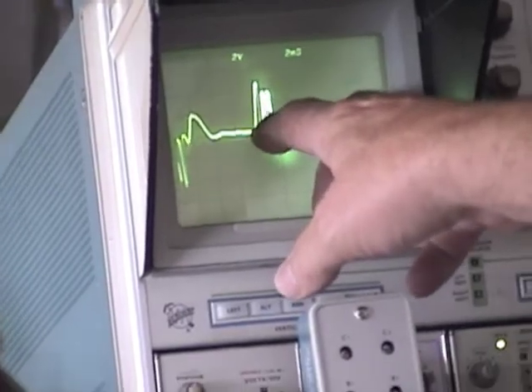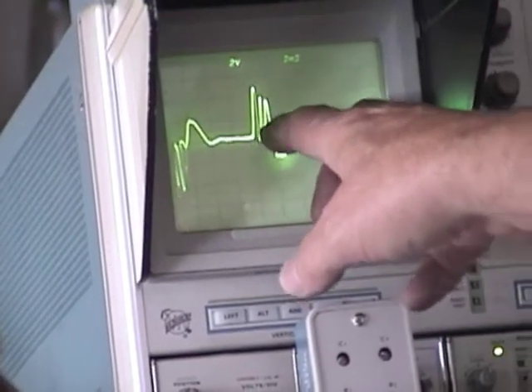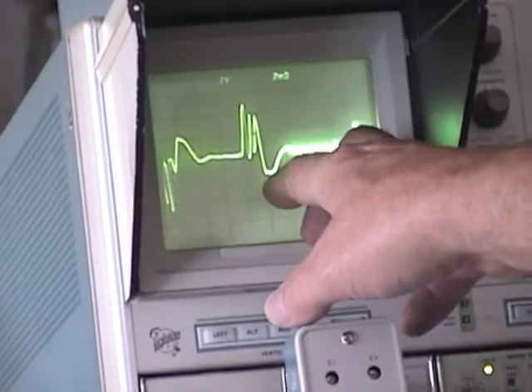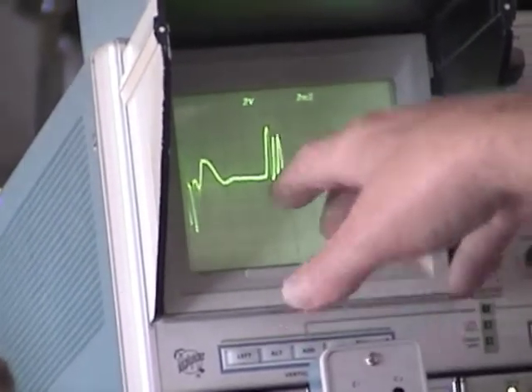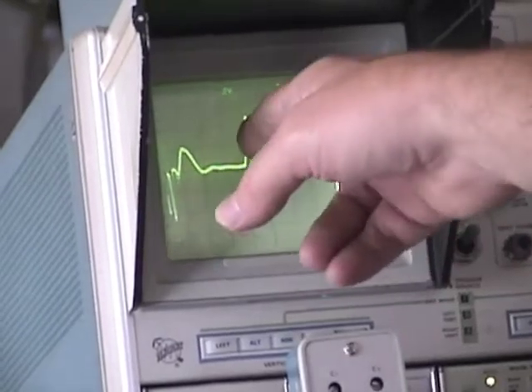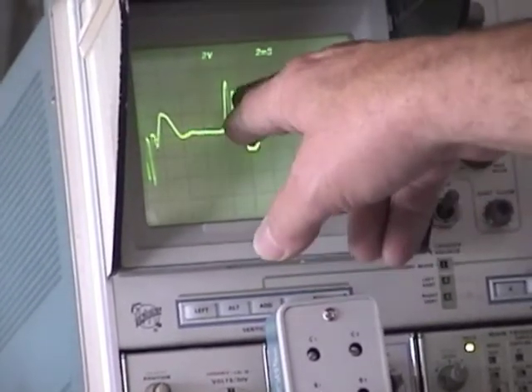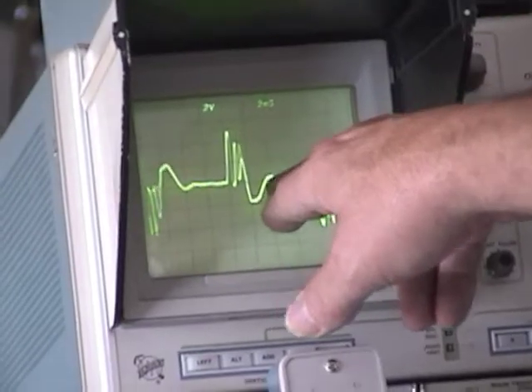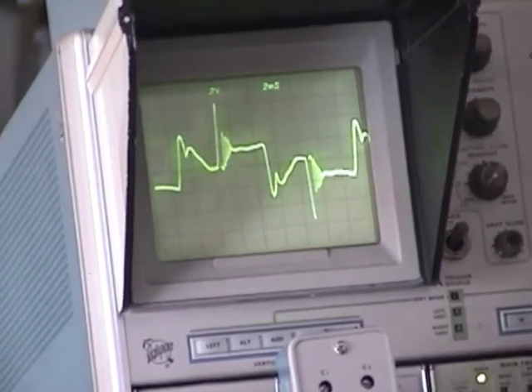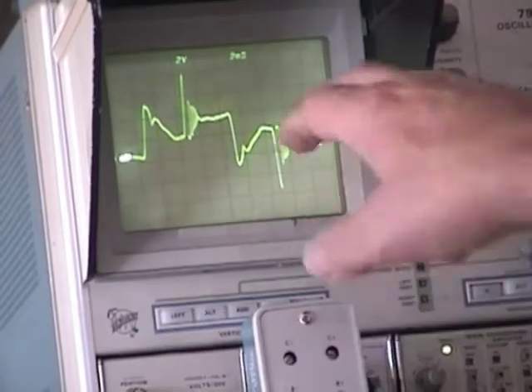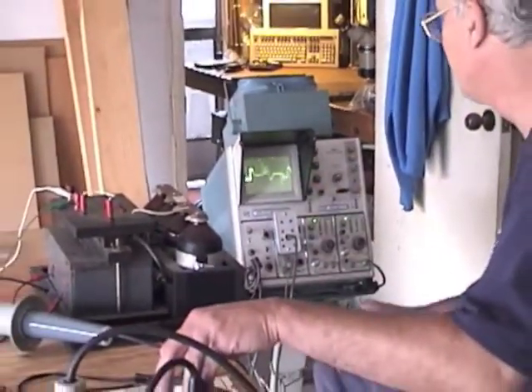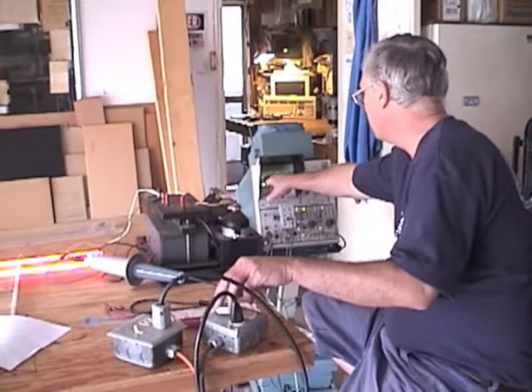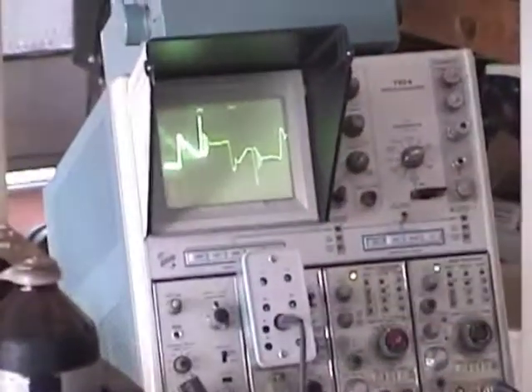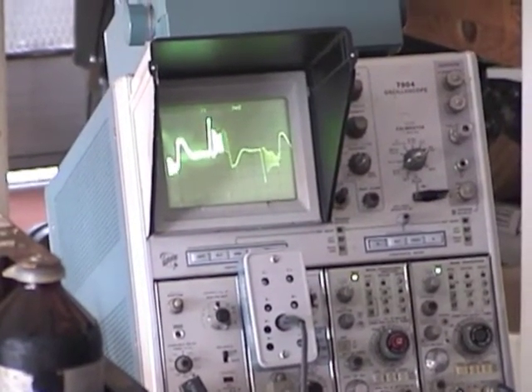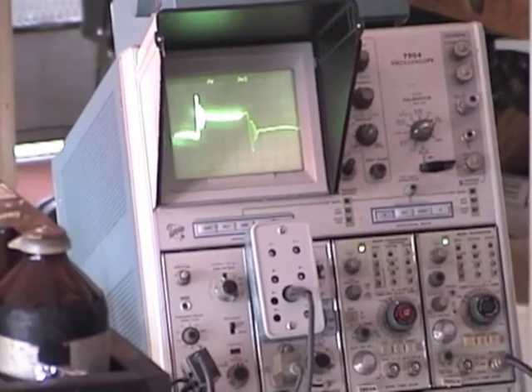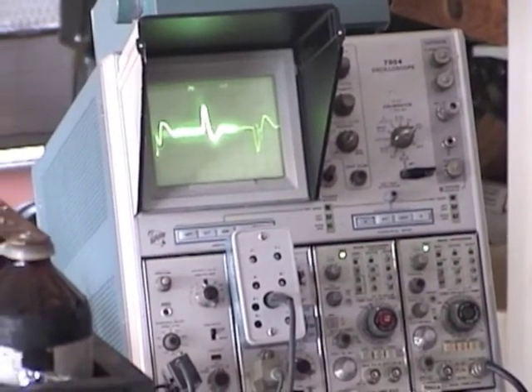Then the dimmer turns on, it rings, the line voltage goes back through 0, but the current is still flowing because the transformer is inductive. So you see the voltage will actually go back through 0, or back through to the negative polarity, then it'll come back to 0. As you change the dimmer, you're changing the width of that on time. So there's on time from there to there, this is the off time from the previous waveform. You turn it all the way up, you get full waveform, you turn it down, you go to 0.